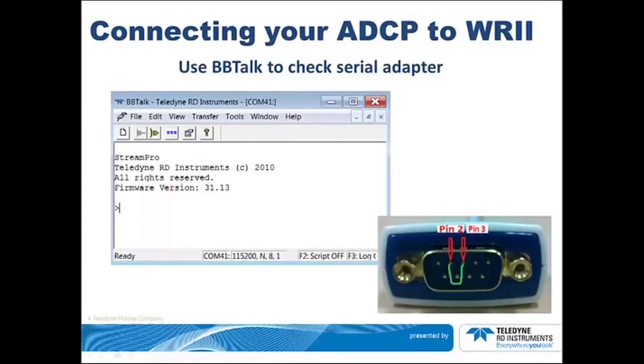Now we are going to use BBtalk to check the serial adapter. If you have any communication issue, it is much easier to troubleshoot using BBtalk than WinRiver 2 or WinH ADCP. If you do not know for sure that the serial adapter works, place a short circuit between pins number 2 and 3 on the 9-pin connector. Note that in this orientation there are 5 pins in the top row and 4 pins in the lower row. Now whatever you type should be echoed back exactly as you typed it.